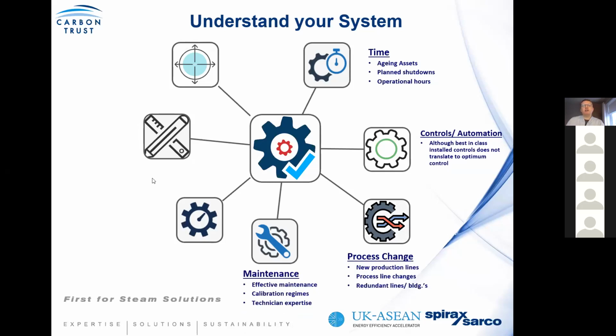Is there a process change? Because what you'll find is that your factory will change over time. If designed 20 years ago, it's probably unlikely that you have the same type of production that you have now. So are there new production lines? Are there process changes, or have some production lines been made redundant? We talked about maintenance, again, effective maintenance and calibration, because when we talked about control, where you have any instruments that have an impact on the efficiency of a system, they should be on a calibration regime to ensure that they're accurate and reliable. And what we're also finding is that sometimes technician expertise could be lacking, not through their own fault, but because the drive for lean operations means that sometimes knowledge is lost.